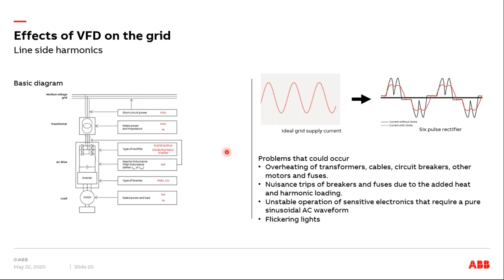It depends upon, and I'll talk a little bit in the next slide about these solutions, but let's look into the problem. So Deepak already mentioned how a VFD works. You have basically a rectifier converting AC to DC, and then you have an inverter section that converts your DC signal to the AC.